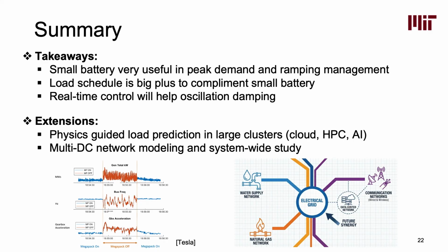But we can see those ramps are pretty large. What they do is, for a very short time window, like 30 seconds, they turn on their batteries, which I think are roughly 200 megawatts and 400 megawatt-hours, using them for fast operations to absorb these additional oscillations here.